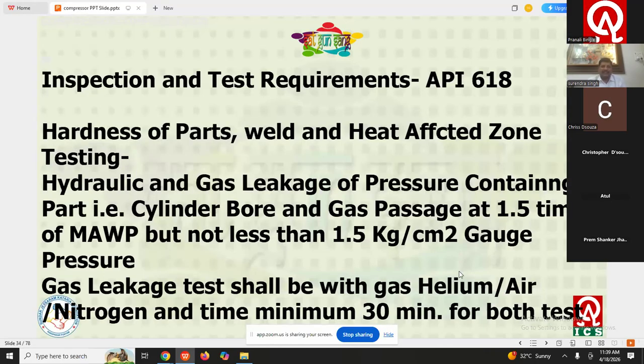Okay, now after the visual inspection, we have to check the hardness of the part, maybe on the parent metal part, then the welding. If welding is there, then we have to check the hardness on the weld area, then on the heat affected zone. Any other testing required in the QP, you also have to witness. Now coming to the testing part, the hydraulic and gas leakage test of the pressure containing parts as per API 618 is to be carried out, that is cylinder bore and gas passage at 1.5 times the maximum allowable working pressure.